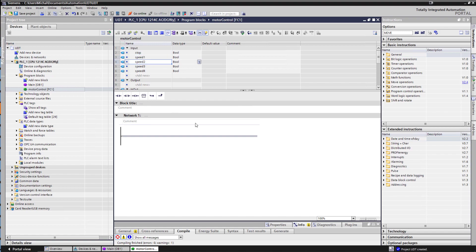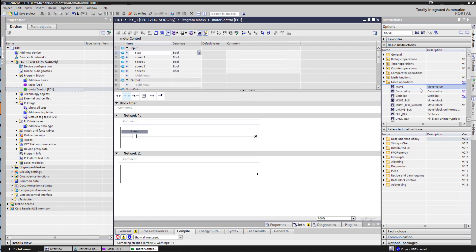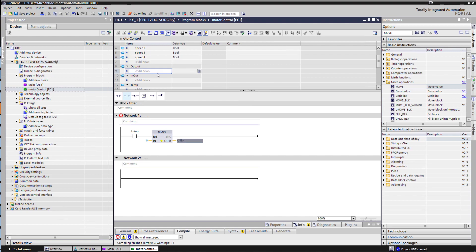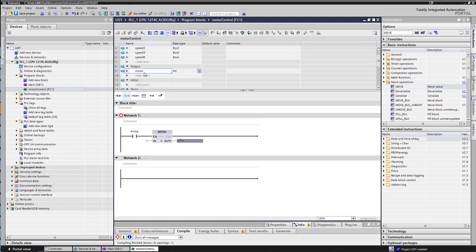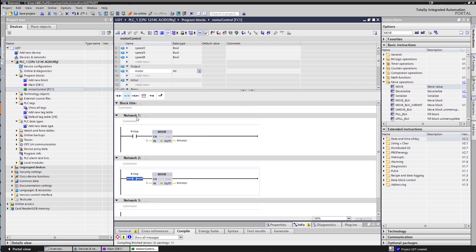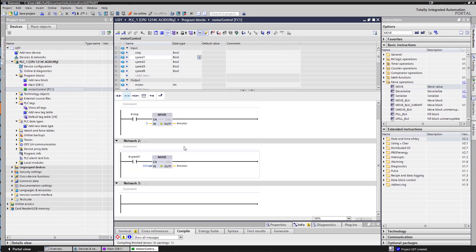So we have five different inputs and what we'd be doing is we'll be saying if stop then we'll be moving zero to an output that is tied to our motor. So we'll call this one motor, it's going to be an integer. Now it might be an input of an analog input of your drive that's driving the motor, we're sending it zero to 10 volts and if it's zero it just switches off. So we send zero to stop the motor and then we will send another command. If we say speed one it's going to be going in slow mode, maybe 300 rpm.